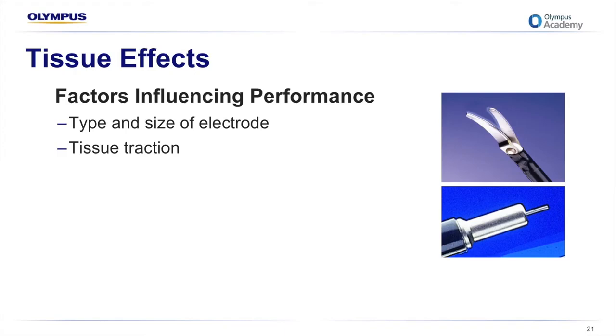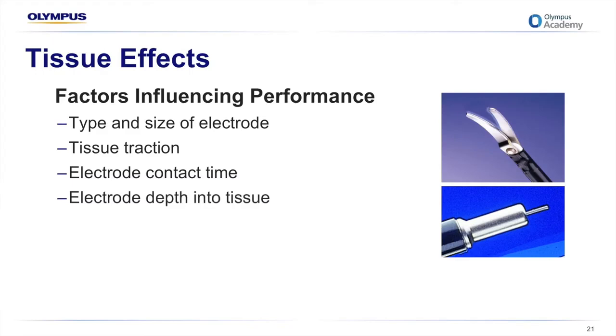Tissue traction will provide a smaller contact point for the electrode. The length of time the surgeon maintains contact with the targeted tissue will influence the cutting action. The longer the contact, the greater the thermal spread. Embedding the electrode too far into tissue will result in less cutting and more coagulation. Different types of tissue can respond differently to the current.